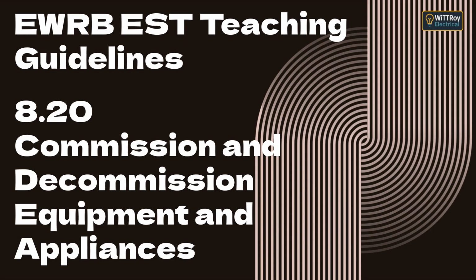Step 4. Reconnection and rotation. When reconnecting, check that your safety tag is still in place and isolation is still valid. Do another prove, test, prove. Then reconnect each conductor to its terminal, tightening the screws to the manufacturer's torque if specified. For three-phase motors, confirm correct direction of rotation by momentarily running the motor under supervision. If rotation is wrong, swap any two-phase conductors. Always test earthing, polarity, and insulation resistance before replacing covers and guards. In short, isolate, identify, make safe, reconnect, test and verify rotation.